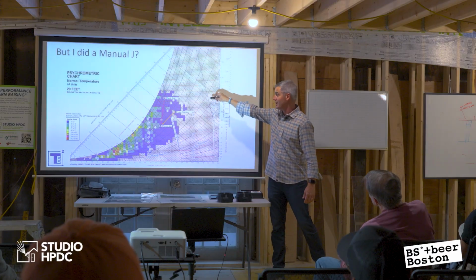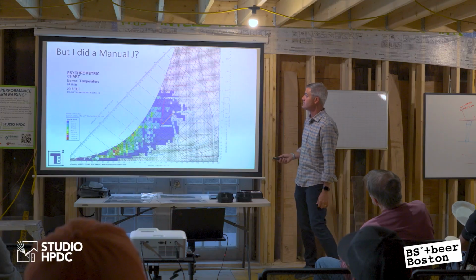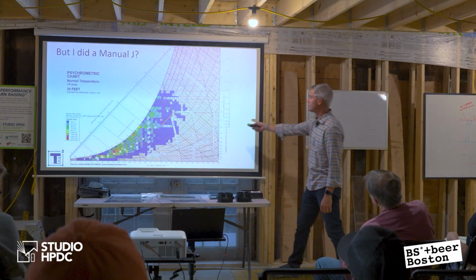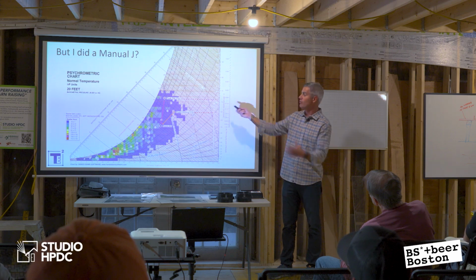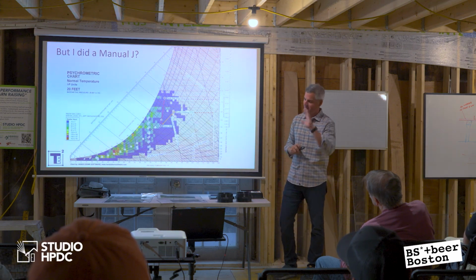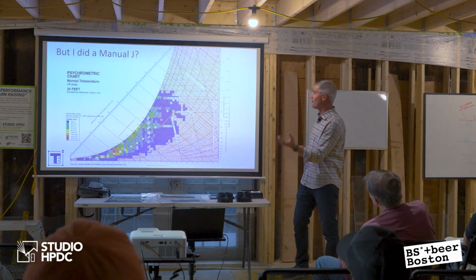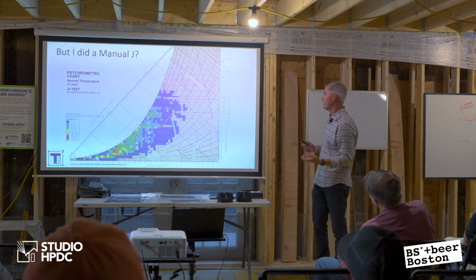But this is what our cooling system might have to do, and that's why supplemental dehumidification comes up in a lot of projects now. And look at the different grains. 90 grains versus 115 grains. So we measure moisture in grains. I don't want to go into why that's great. It's a long story, but basically it's how many grains of moisture per pound of dry air. That's the ratio, and that's what they call the humidity ratio.